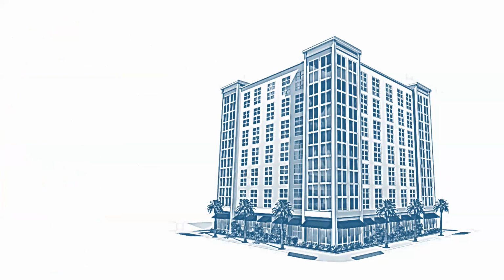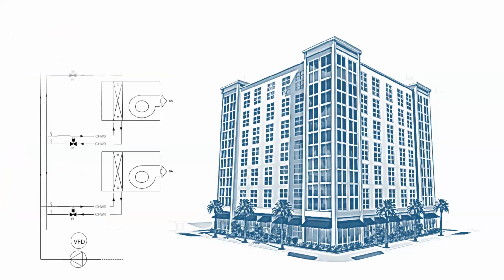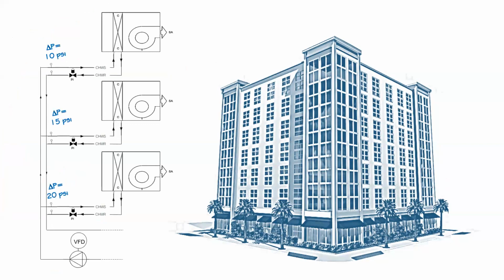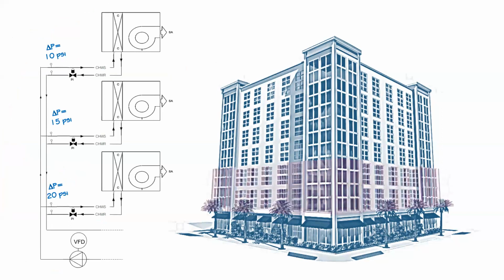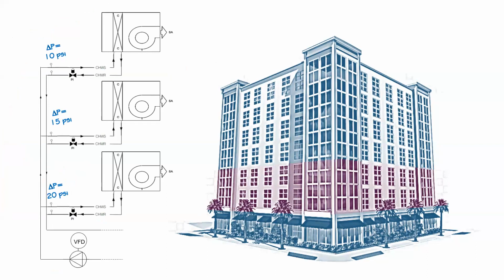So now let's take that same building and pipe it with pressure independent valves. So we'll have the same pressure drops as before, but all of the zones are now hydronically isolated from one another. That same firm goes home at noon. The valve closes. Pressure drop and flow go to 0. Other zones overpressurize. But the pressure independent valves are unaffected by this overpressurization.